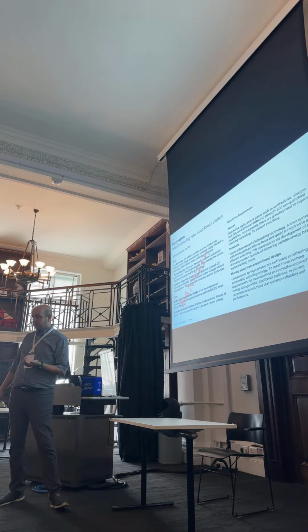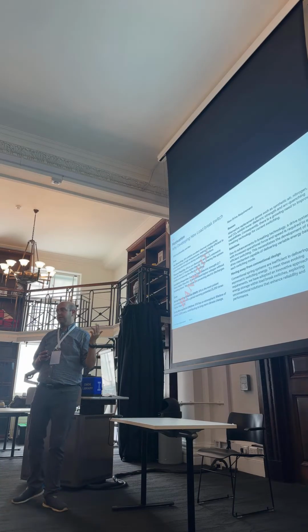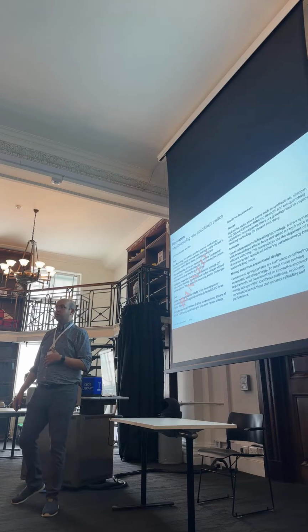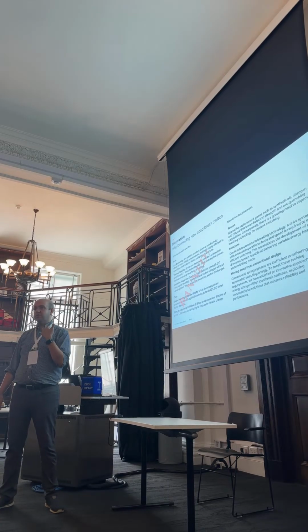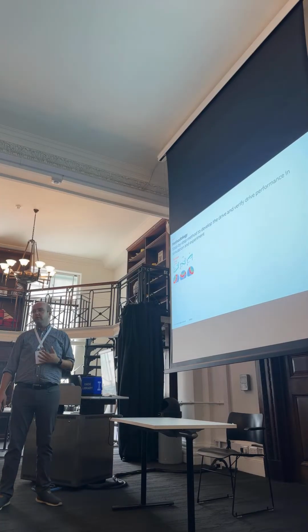So this ban came, and now we need to come up with a new solution. One of the solutions is to get a similar behavior by increasing the pressure inside the chamber. Previously with SF6, we could work at 1 bar absolute pressure, so 0 bar gauge. But if you want to go with dry air, so air with the moisture taken out of it, we need to increase the pressure to 2.5 to 3 bar for the application. And this increase of pressure means the drive needs to provide a higher amount of energy, and we need a different type of energy release for such a system. That's why we came up with our new design called floating spring.